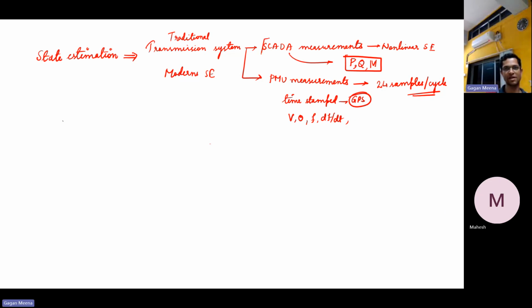Here, with SCADA measurements, the sampling rate is quite small as compared to PMU. PMU samples at a much higher rate. So we can directly get the voltage and angle information, frequency, and df by dt. So this has changed things. Now this has made the state estimator linear. We can use a linear state estimator instead of a non-linear one. Yeah, this was a major breakthrough, and because of using linear, it becomes quite fast. Since the data we are receiving is also coming at a very fast rate, we need to process it very fast, and because of the LP framework, we are able to achieve that faster processing of the data.